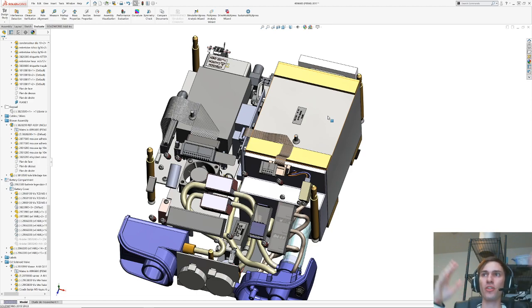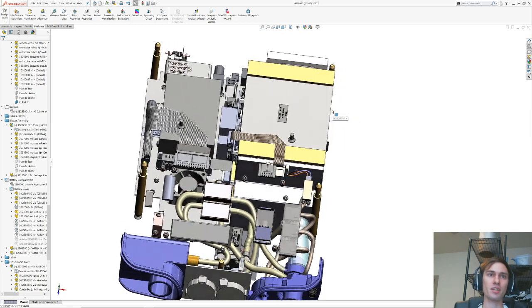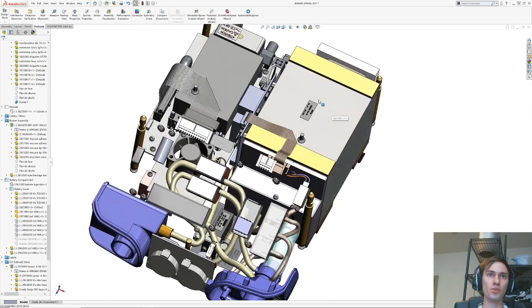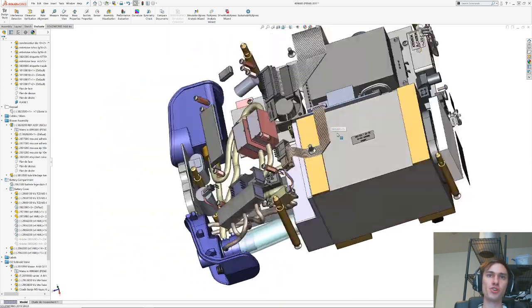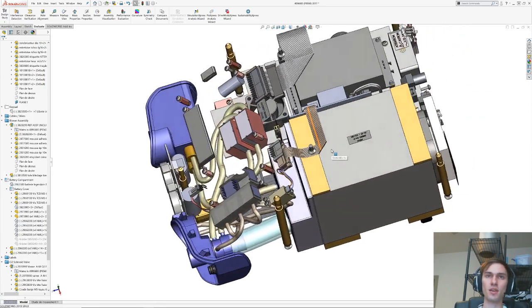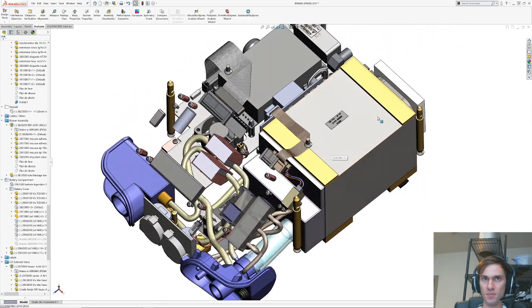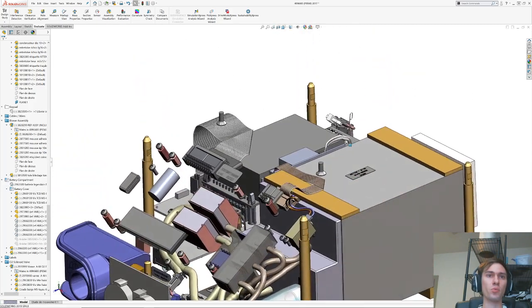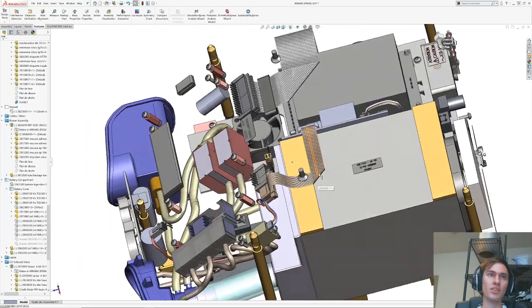So the tidal volume is the amount of air that goes into the lungs. By adjusting the valve timing, you can control the tidal volume without having to mechanically adjust things. And you can also adjust the pressure delivered by controlling the speed of this blower. You don't even need a half PSI of air. So I think this is actually a really good way to do it that more people should be looking into. I've bought some high-powered drone motors to try and rig our own CPAP machine. That seems like a good way to try and do this. Okay, so that's what I think this is.